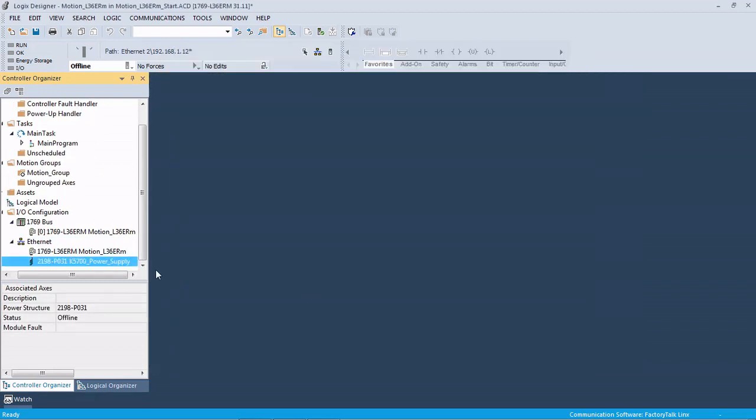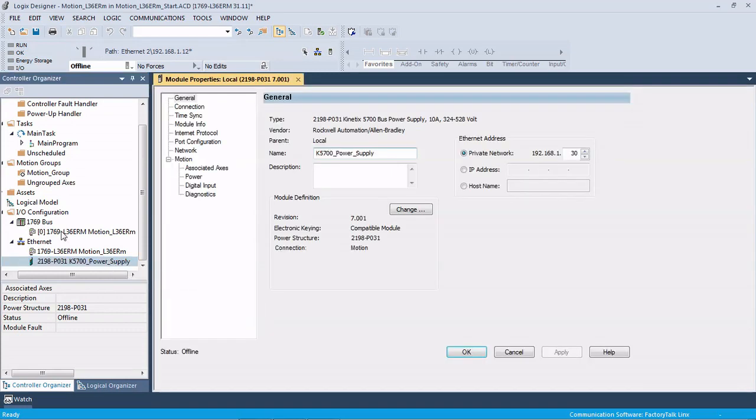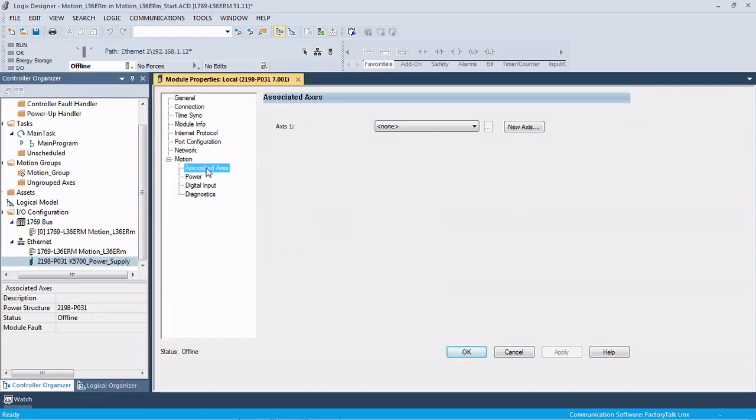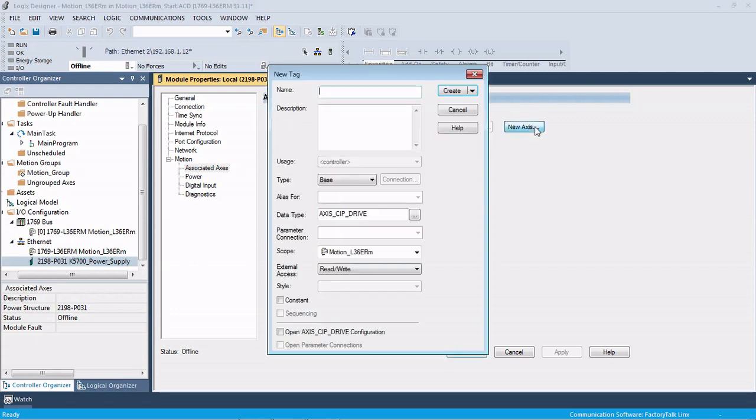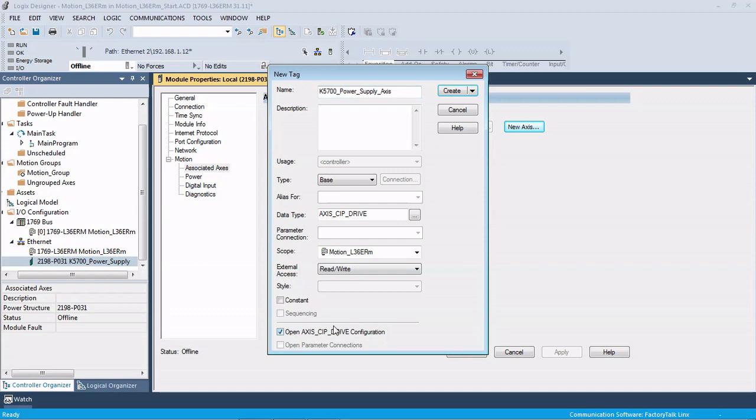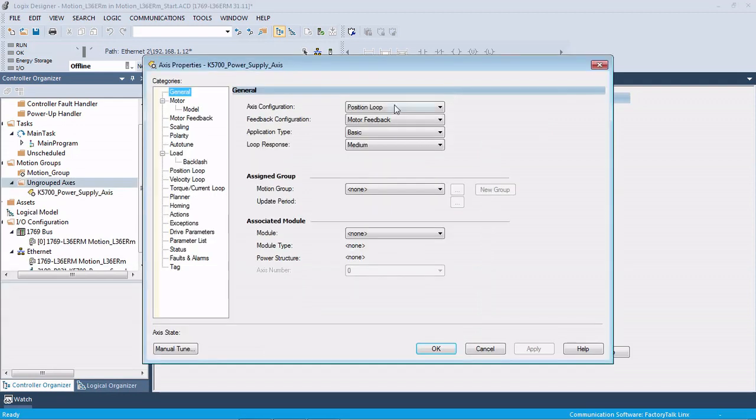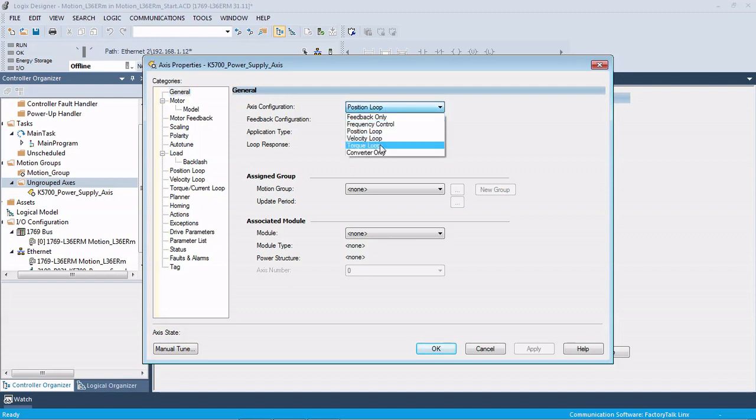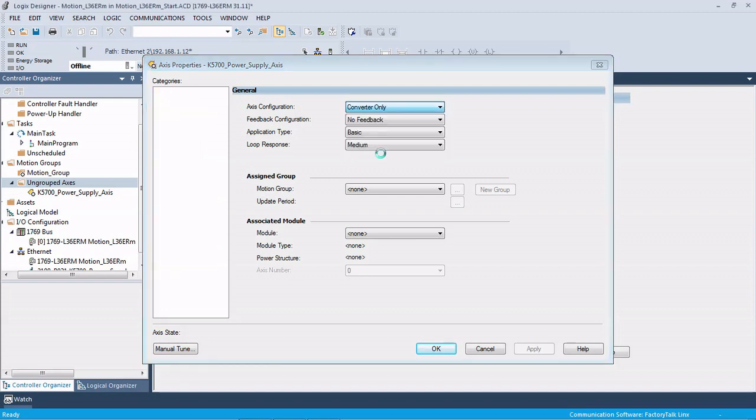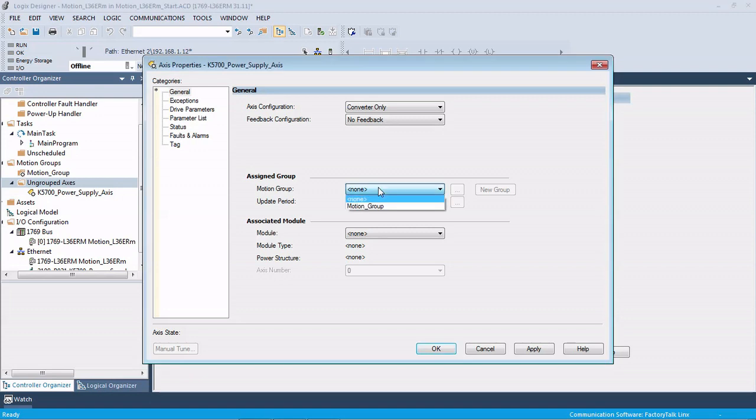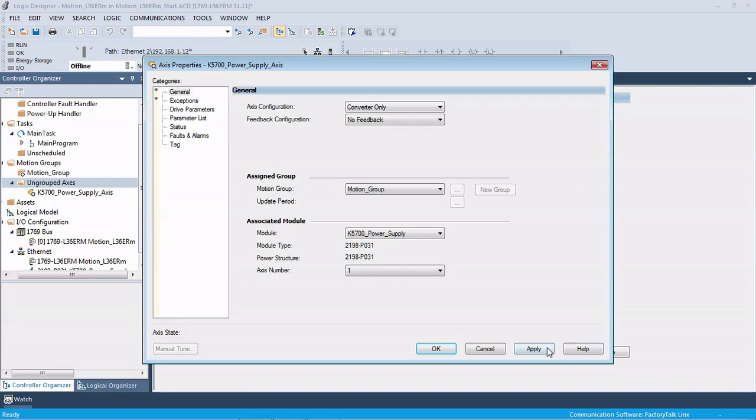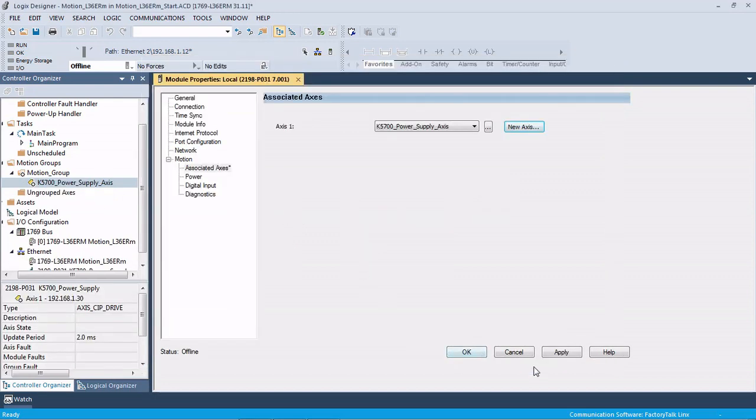Next thing we're going to do is bring up the properties for that power supply. Under associated axes we have none. You do have to actually create an axis for the power supply even though there's not a physical axis. We're going to click new axis and call it Kinetics 5700 power axis. Since we're not controlling the actual position of a physical axis, we're going to change this to converter only and assign it to our motion group.